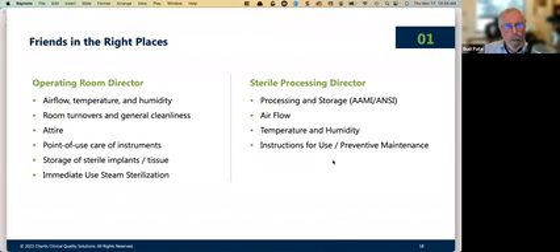Sorry about that. One of the things that's still a problem or challenge is airflow, temperature, and humidity. There's a disconnect—when we deal with this in the OR procedure area, somebody comes in and takes the temperature or humidity reading at the beginning of the day, and because it's a bad reading, they'll log it and then nothing happens about it.